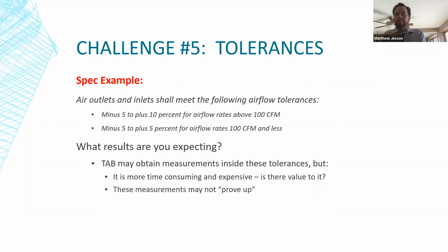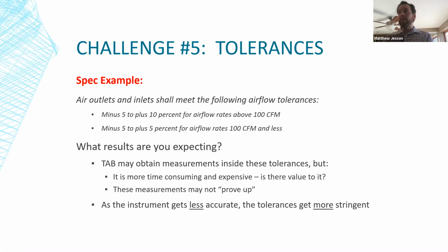The other thing to keep in mind is that the measurements may not prove up based on these accuracies. If you have an outlet that requires 50 CFM and the balancer gets it down to 50 CFM, you might come out with a different balancer with a different hood, both of them perfectly qualified, both hoods working perfectly fine, and you might get a reading of 55 CFM or even further away. So it might not prove up to be within that tolerance that's specified. My big problem with this specification really is that as our ability to measure the airflow gets less accurate, the tolerance gets more stringent. This whole -5 to plus 5% when you get down below 100 CFM is going the wrong way as far as the ability to measure it properly goes.